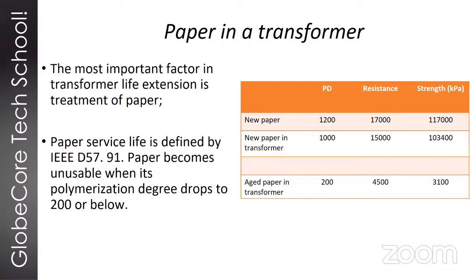So anyway, 200 degree of polymerization is basically the end of transformer paper. When it falls down to, thank you, gentlemen. Well, anyway, as the degree of polymerization drops to 200, that's about it. This is the time that you cannot use the transformer again. And basically, this 200 is set in stone. It's in the IEEE standard.